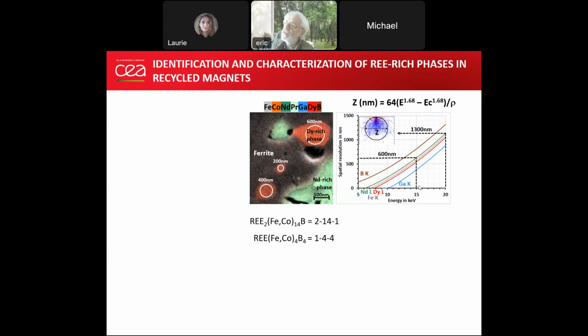So you see from this diagram that if we use 15 kilovolts, the minimum spatial resolution we can get is 600 nanometers. I mean that X-rays are coming from all this region, which is 600 nanometers. So it's not possible to measure particles as small as 200 nanometers. So the first problem is a problem of X-ray spatial resolution, which is quite limited if you work at relatively high voltage, and if you want to measure the K line and L line of your element.